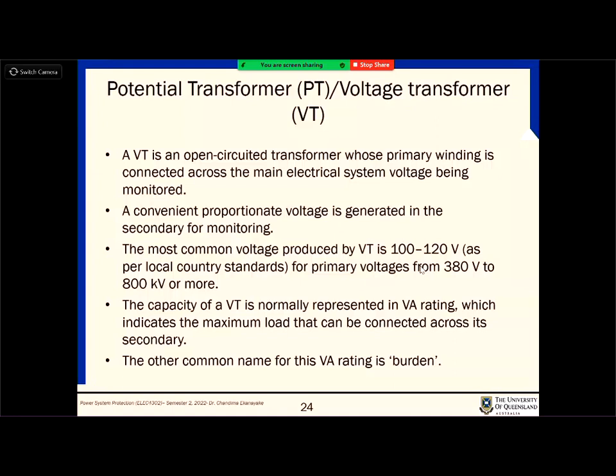And then the primary voltage can go up to even 1 megavolt, right? It depends on the transmission system you are working on. And the power levels are given in VA, represented by VA ratings, right? Capacity or power ratings, which indicate the maximum load that can be connected across the secondary. Not like in the CTs, in a VT you need to connect higher impedances, because the secondary is not driven by the primary current. The secondary is driven by the voltage. So in the secondary circuit you want to have lower magnitudes of current, which means you need higher impedances across the secondary terminals.